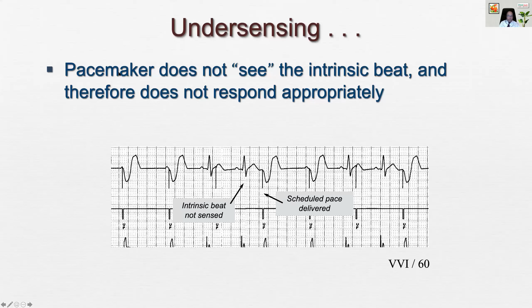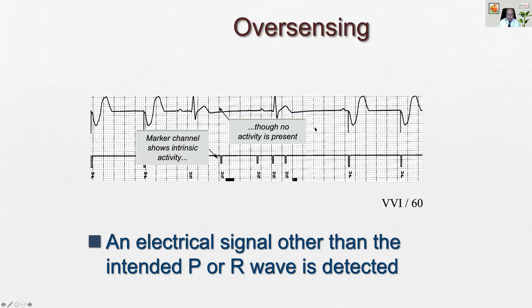On the other hand, there may be a thing called oversensing. In this case, the pacemaker is programmed to VVI 60, which means the pacemaker should sense for 1 second and then give a pulse. But here it is sensing, say, 1, 2, 3, 4, 5. The pacemaker should have given a spike somewhere here, but has not. Even though there is no activity present, something else is sensed from outside, so that is oversensing. You can see in the marker channel that there is some extraneous sensing. So the pacemaker is oversensing and getting inhibited when it should not have been. The way we program sensitivity is in millivolts again. We have certain sensitivity, and the higher the programmed value, the lower the sensitivity.